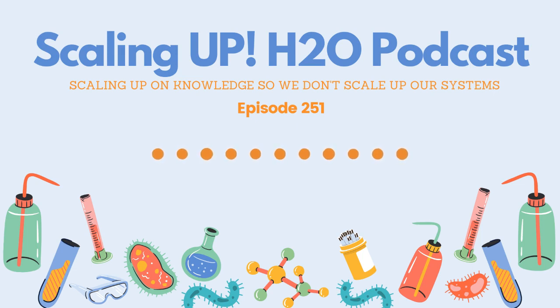Put your test kit down somewhere safe, off to the side, and now walk around. Have a conversation with the equipment. If it's a chiller, look at the chiller. Is everything the same as you remember it? Maybe go into the user interface and see if all the readouts you can check on that machine are normal.